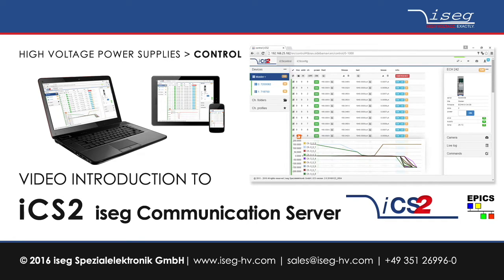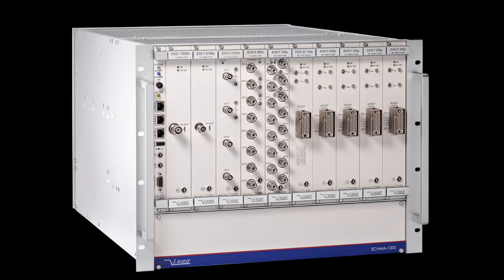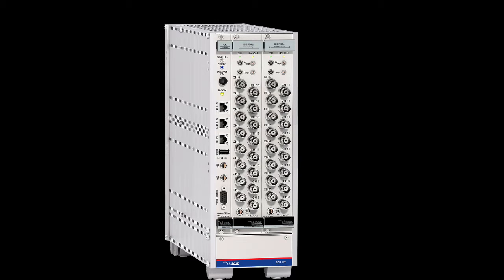The ICS2 is designed to offer easy access to monitor and control of the extensive product range of iseg multichannel high voltage modules and the various crates which are offered. A system always consists of at least one ICS2 server, one crate controller, one crate, and one high voltage module.